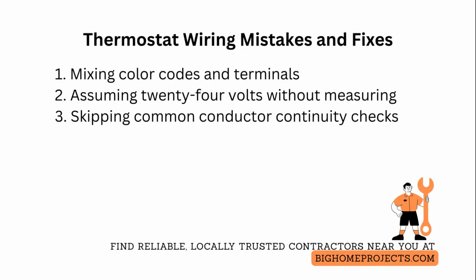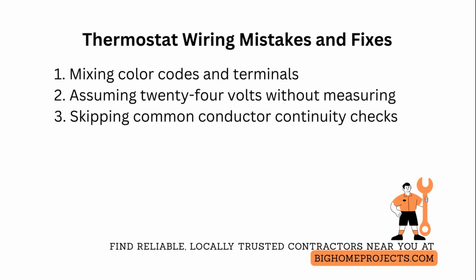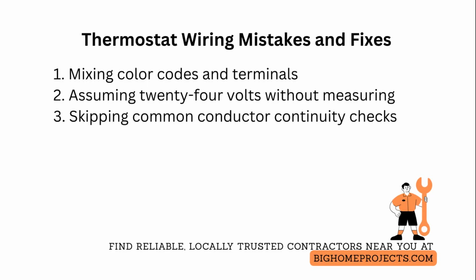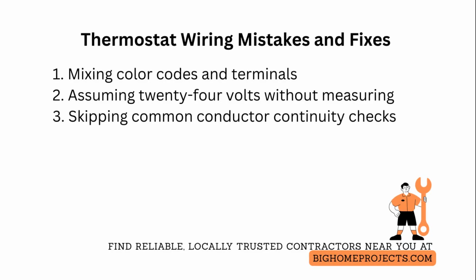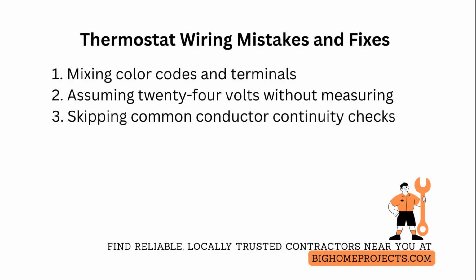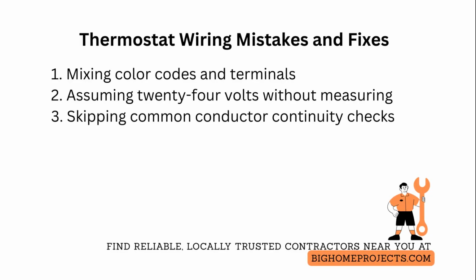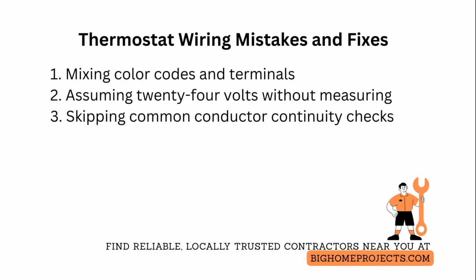thermostats. Fix that by measuring with a multimeter between the power and common terminals and replacing or repairing the transformer if voltage is absent or unstable. One of the third common problems is skipping continuity checks on the common conductor, which makes Wi-Fi thermostats behave erratically.